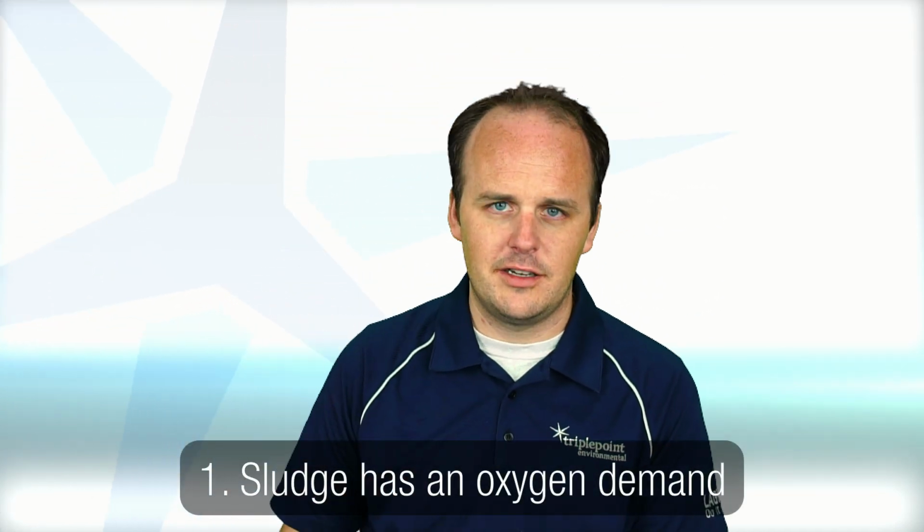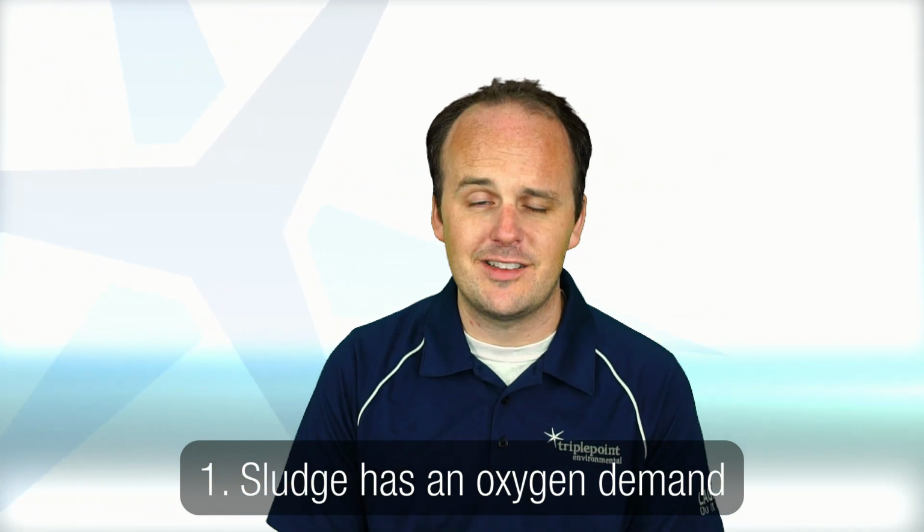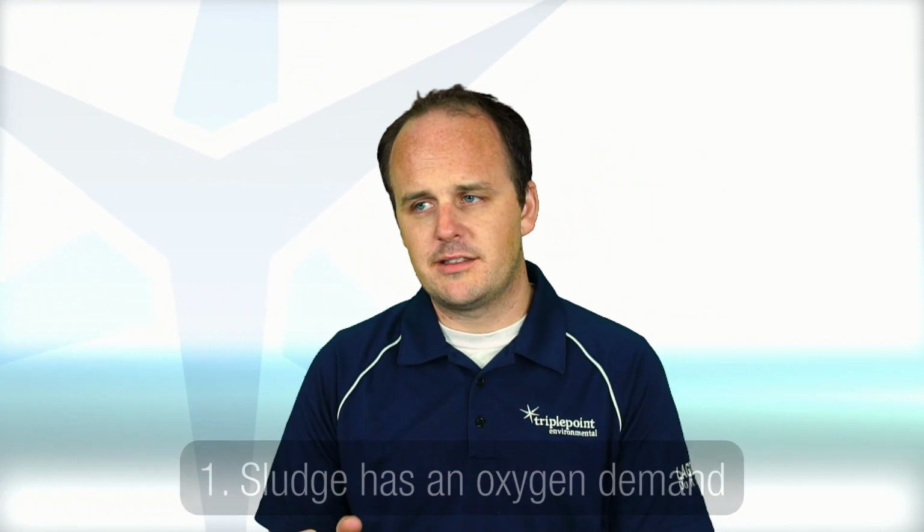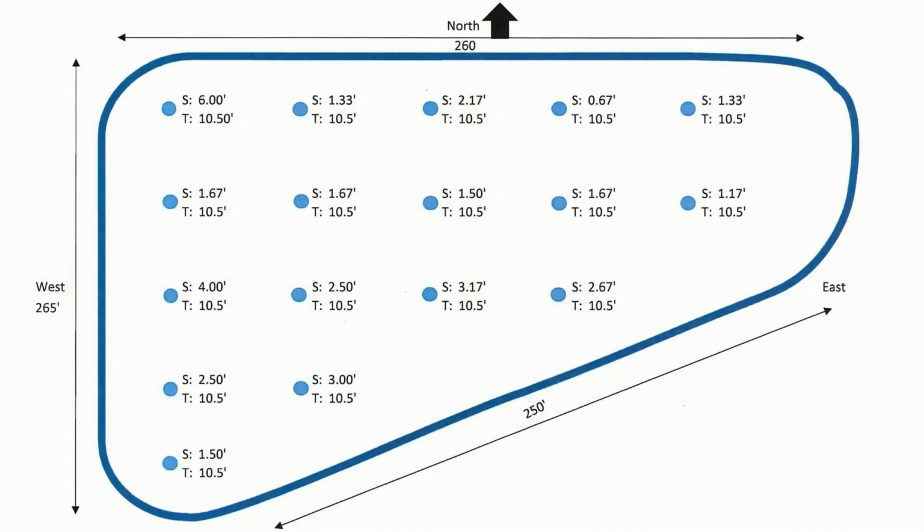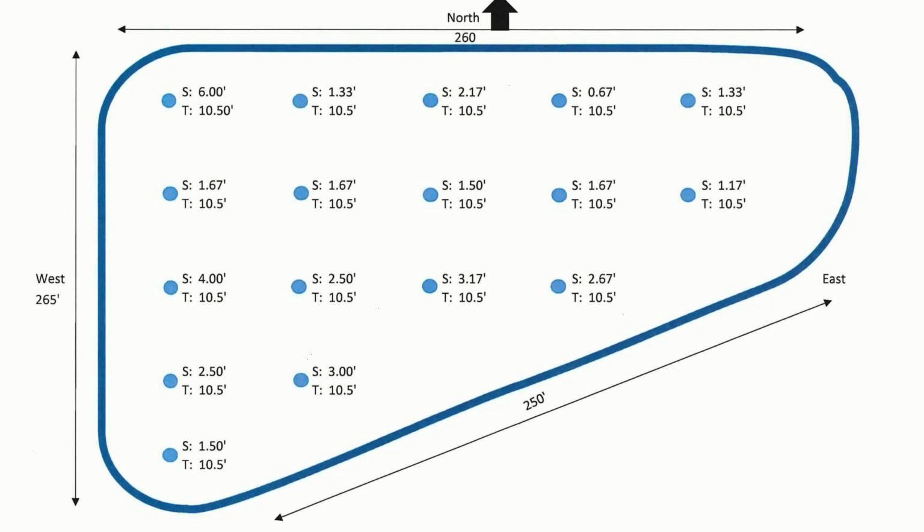Well, we installed our system in 5 feet of sludge. Well, if you have 5 feet of sludge, that is undigested BOD. That requires oxygen too. That's taking in oxygen in addition to the BOD that's already coming into the system. So that is really something that needs to be accounted for and measured, ideally before you even finish up your design, so that you have an understanding of where that sludge level is.